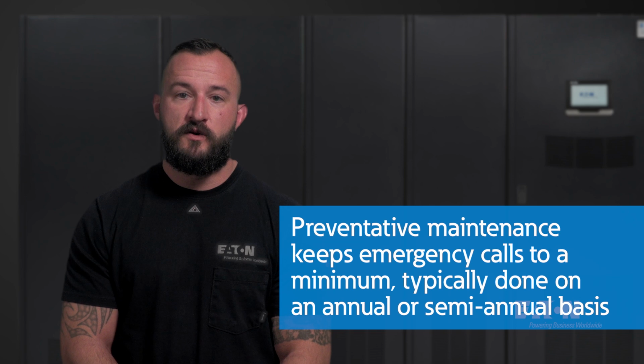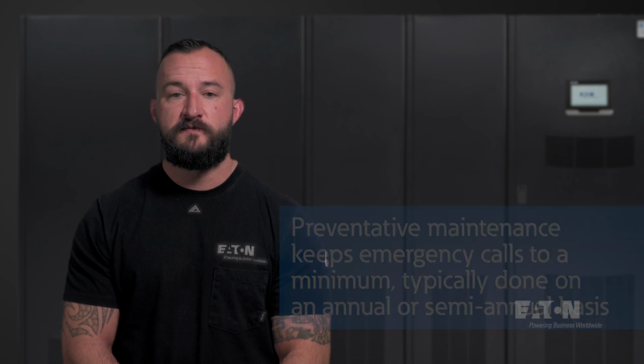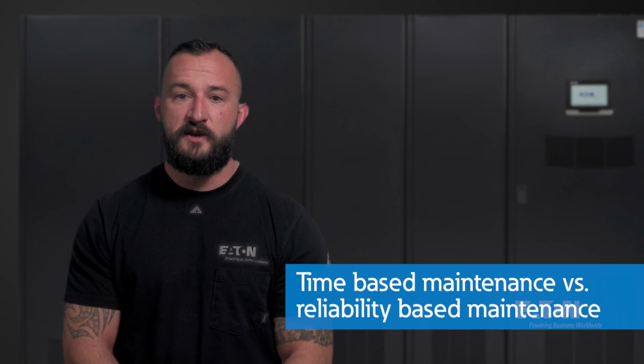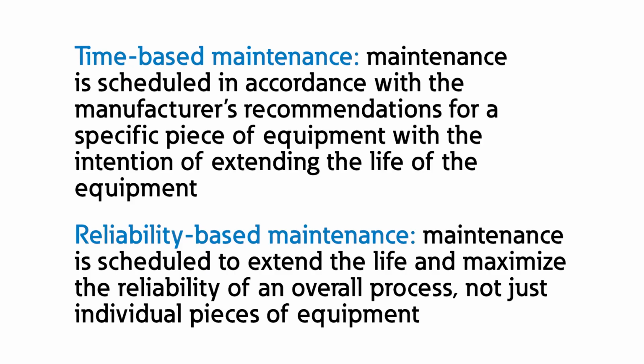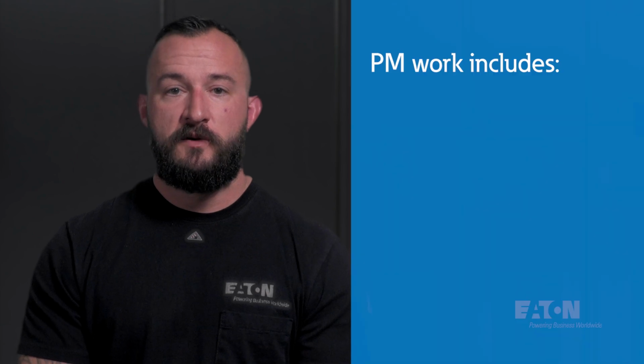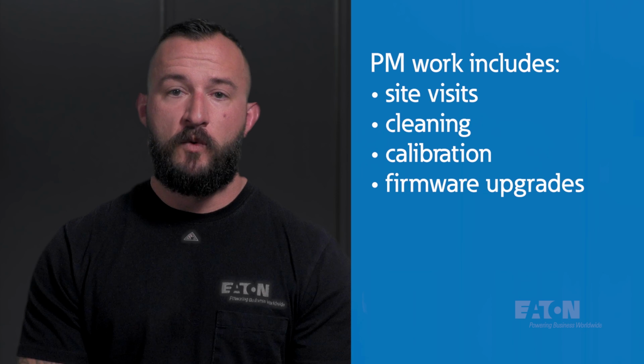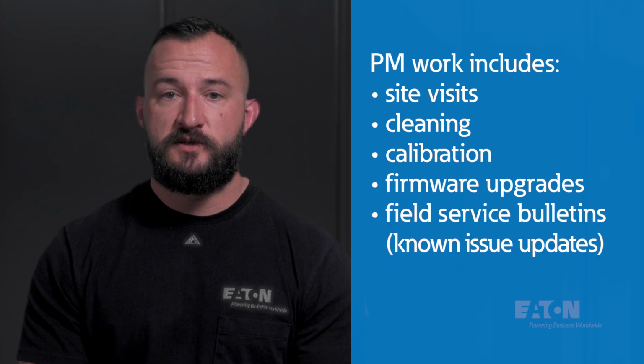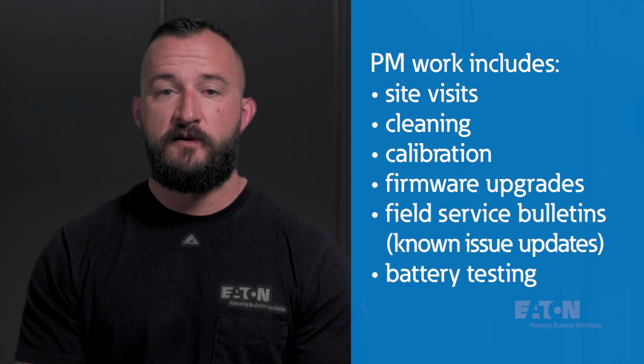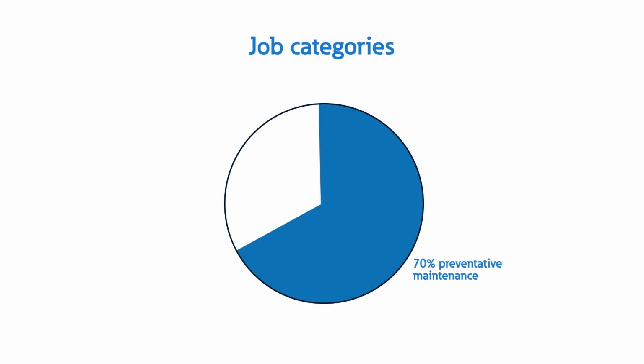PM is typically done on an annual or semi-annual basis. Customers either do time-based maintenance or reliability-based maintenance. If they do reliability-based maintenance, it may be more or less frequent depending on the environment or other factors. In general, PM work includes site visits, cleaning, calibration, firmware upgrades, field service bulletins or known issue updates, and battery testing.